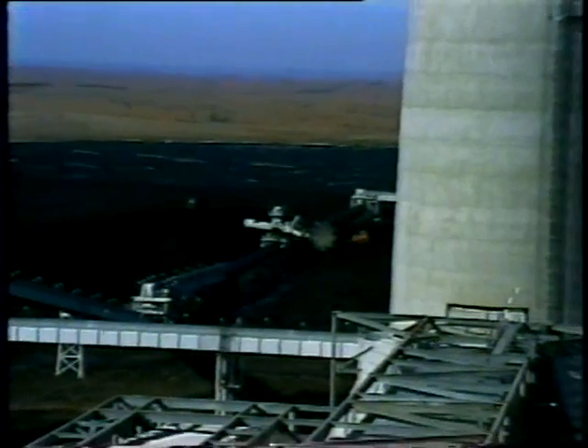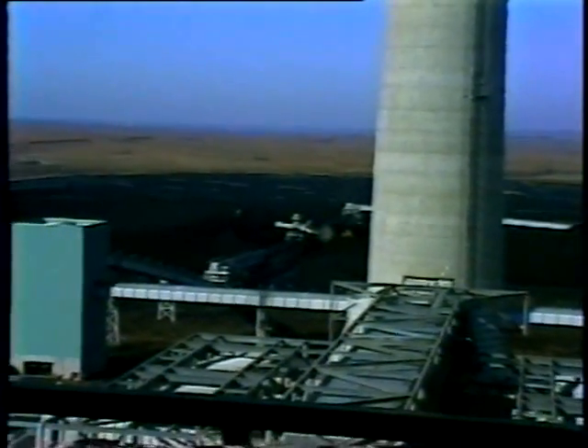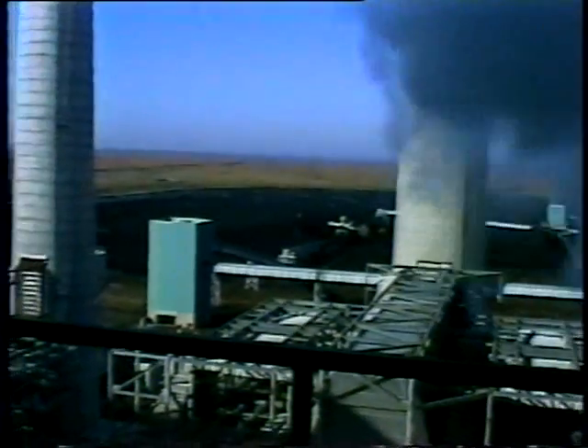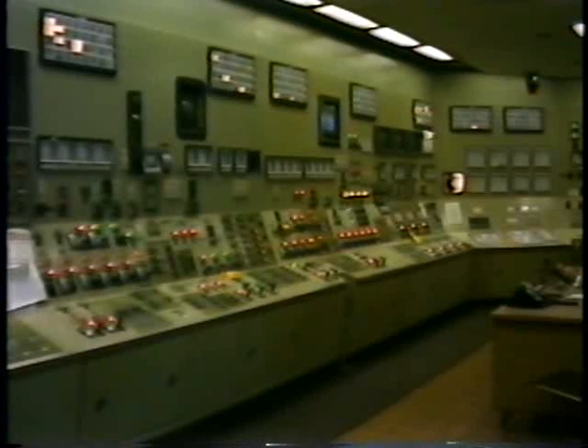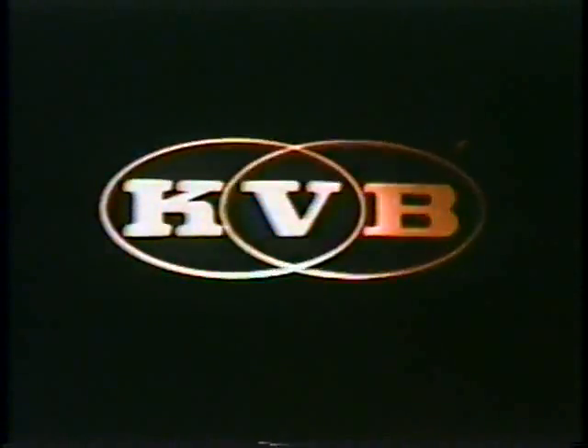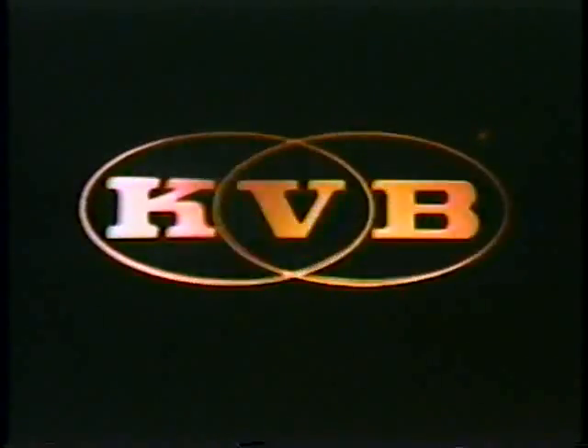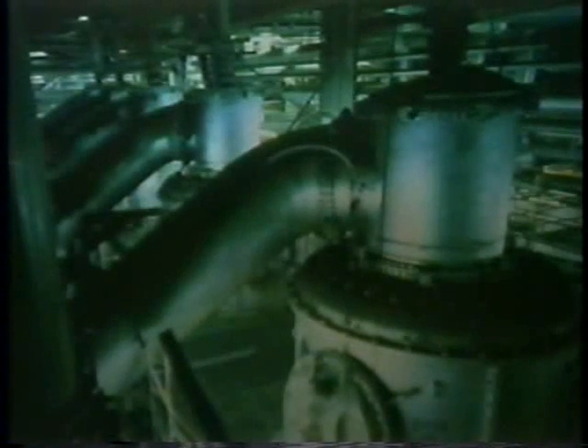Processing coal by drying, grinding, and pulverizing may create conditions conducive to fires and explosions. Until recently, instrumentation often failed to detect the dangerous condition until after the damage was done. Now, KVB, a nationally recognized leader in combustion research and engineering, has developed and produced a fully automated coal fire protection system. It detects and predicts an impending fire and explosion and provides sufficient warning to take corrective action. The KVB Coal Fire Protection System guards against coal fires and explosions before they start.